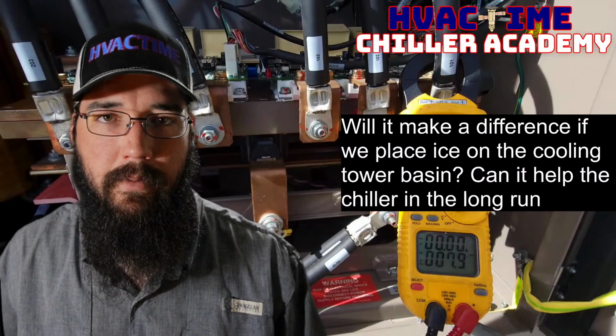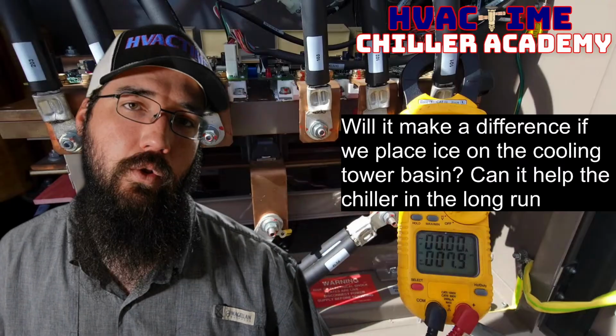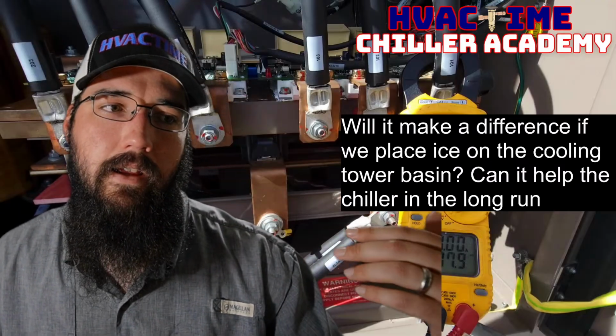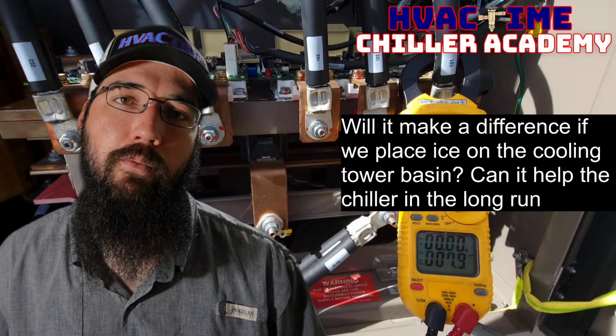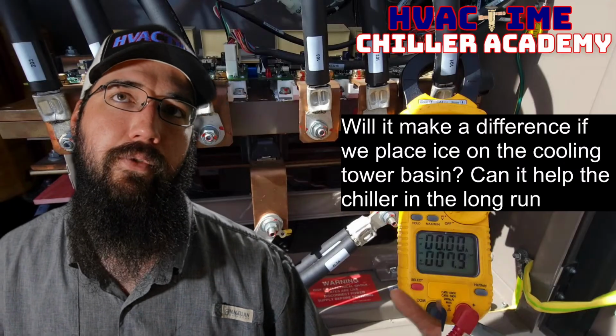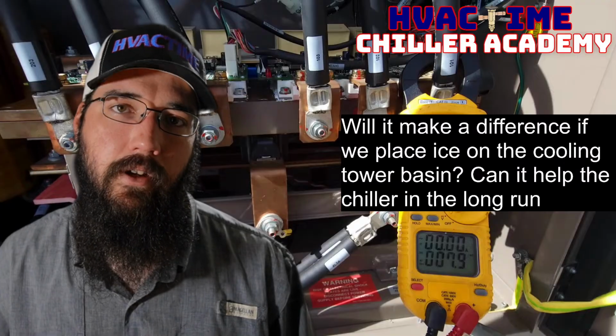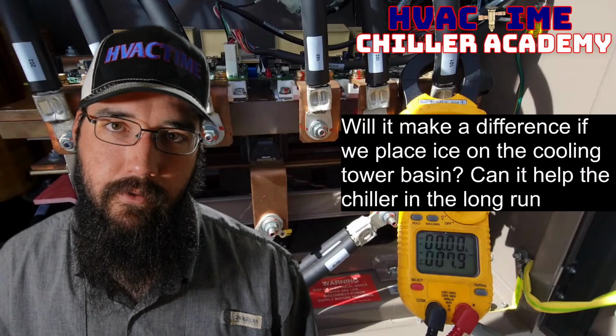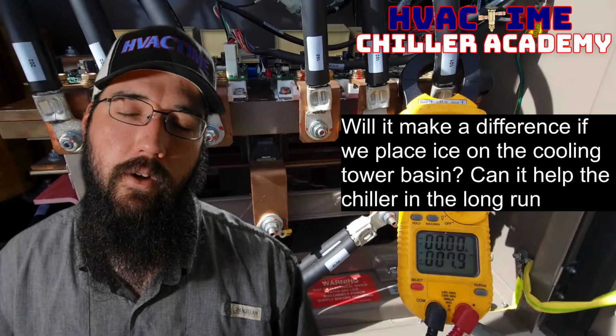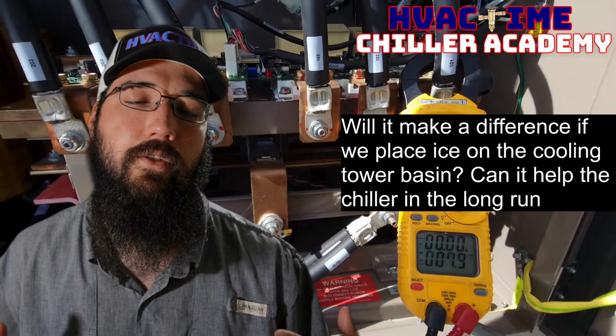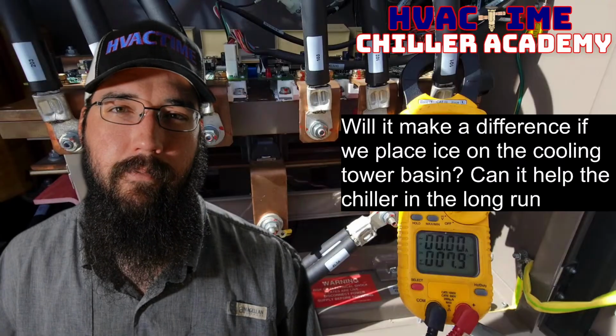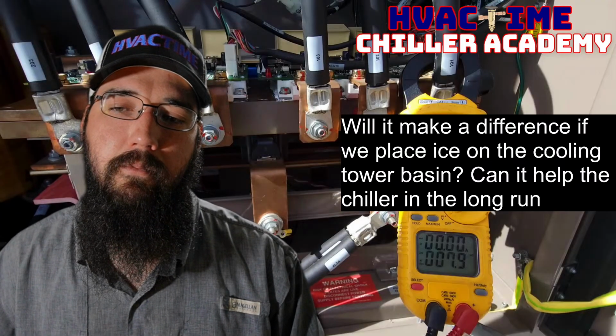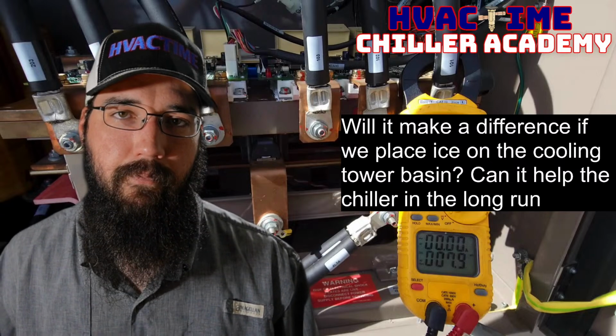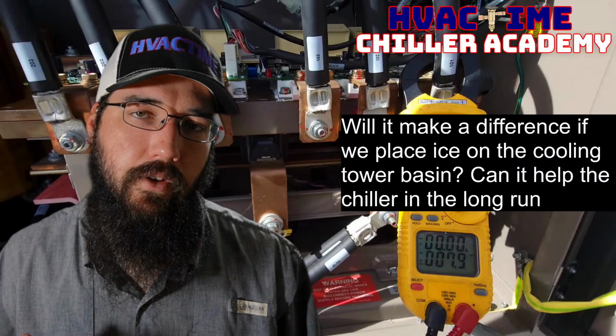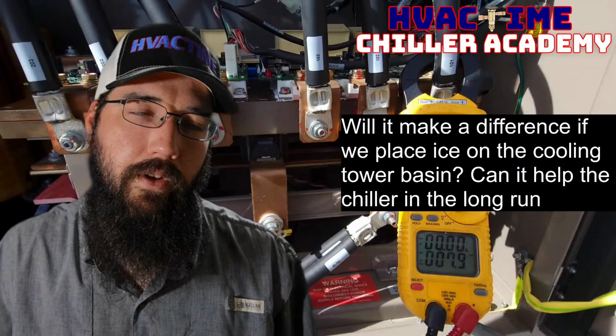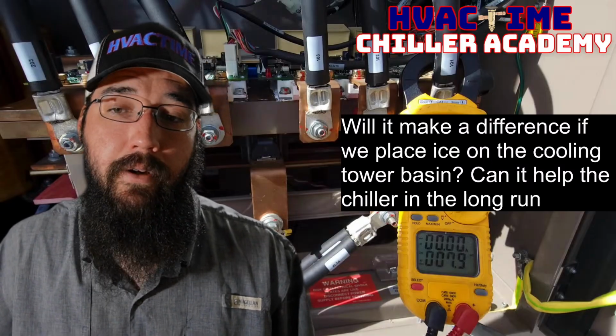So can it help the chiller in the long run? I mean, again, this does come back to we can only go so cold at the same time. So if doing this method and adding ice also means that we start pushing the lower boundaries of how cold of condenser water we're feeding to the chiller, well, then we get back into oil migration territory where we're not properly pulling the oil back into the sump, and the oil recovery system in the chiller, the eductors, aren't able to function correctly, right? So at the same time, in all fairness, as long as we're within those parameters, the lower we can maintain that condenser water within the safety limits of that particular chiller, yeah, the better it is for the chiller in the long run.